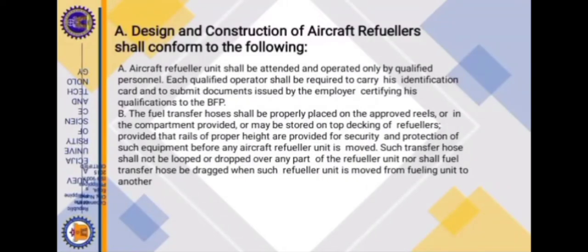A. Design and construction of aircraft refuelers shall conform to the following: Aircraft refueler units shall be attended and operated only by qualified personnel. Each qualified operator shall be required to carry his identification card and to submit documents issued by the employer certifying his qualification to the BFP. The fuel transfer hoses shall be properly placed in the approved reels or in the compartment provided, or may be stored on top decking of the refuelers, provided the rails are of proper height and provide security and protection of such equipment before any aircraft refueler unit is moved. Such transfer hose shall not be looped or dropped over any part of the refueler unit, nor shall the fuel transfer hose be dragged when such refueler unit is moved from one fueling point to another.